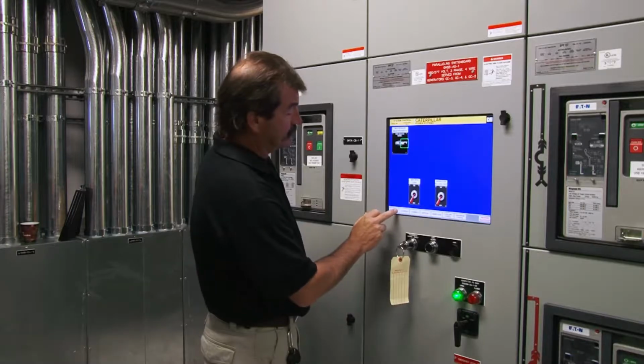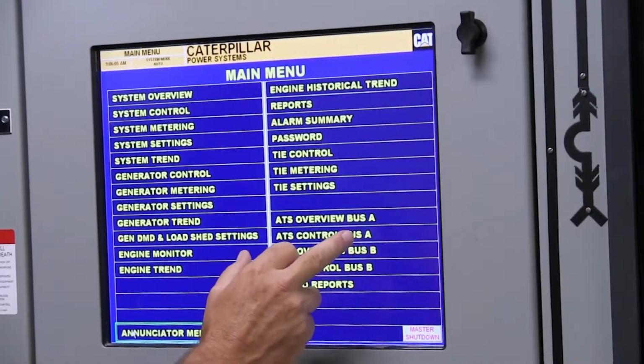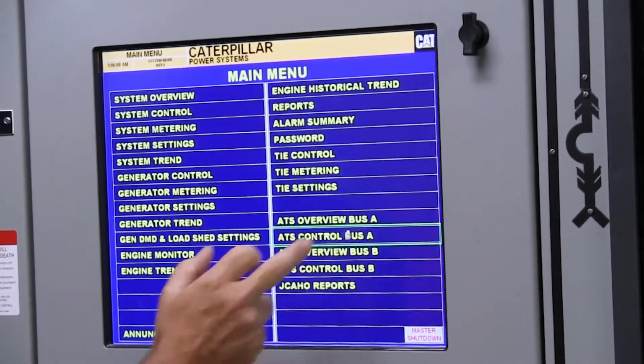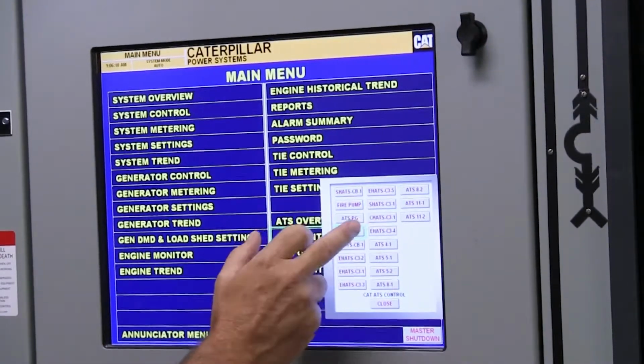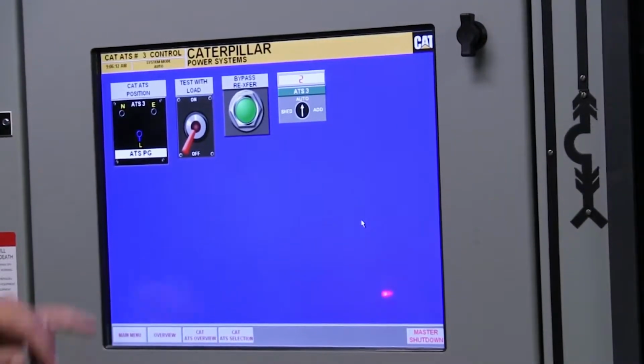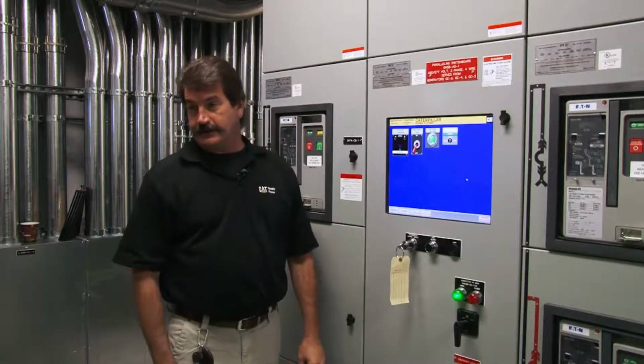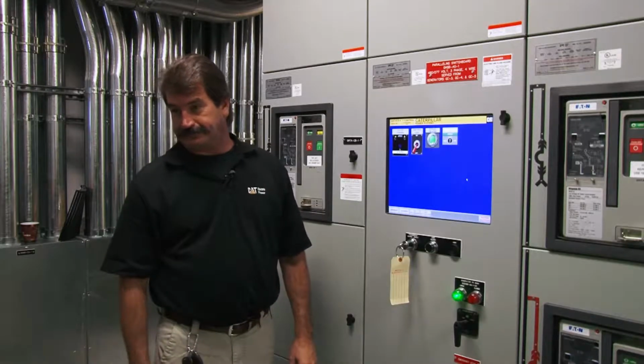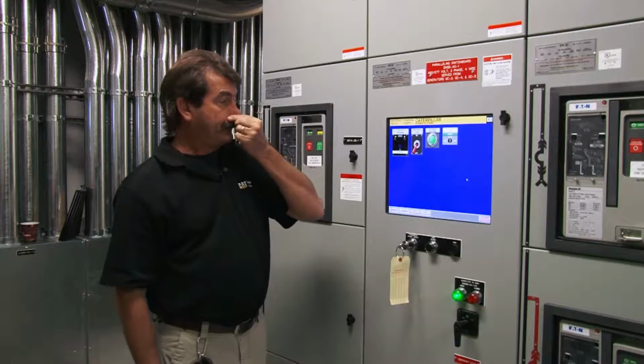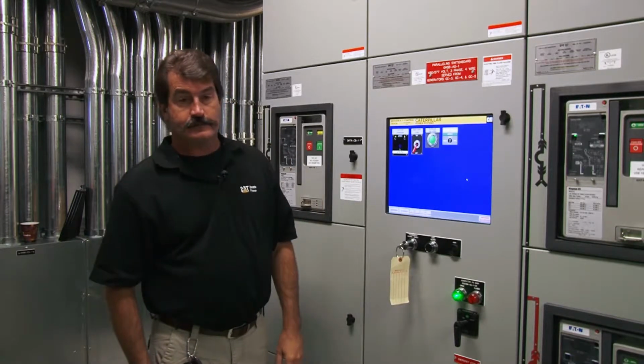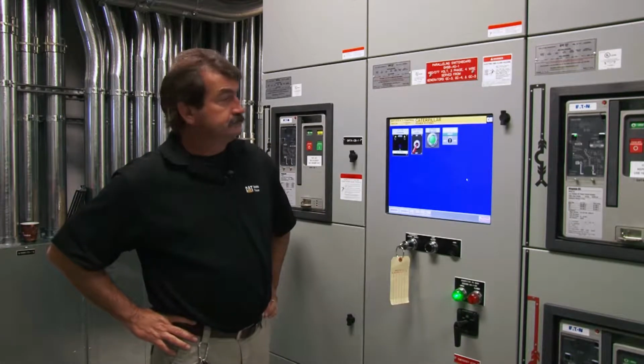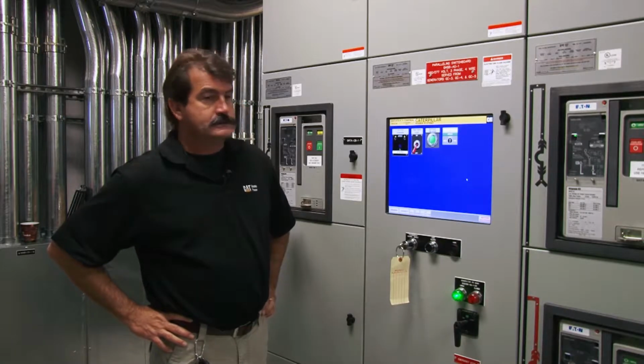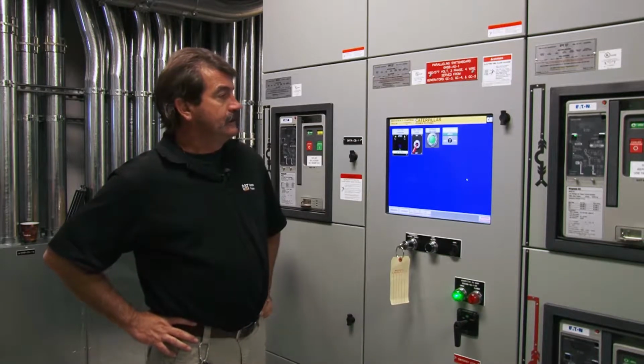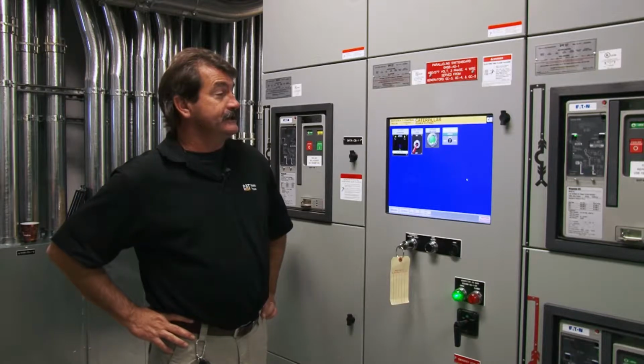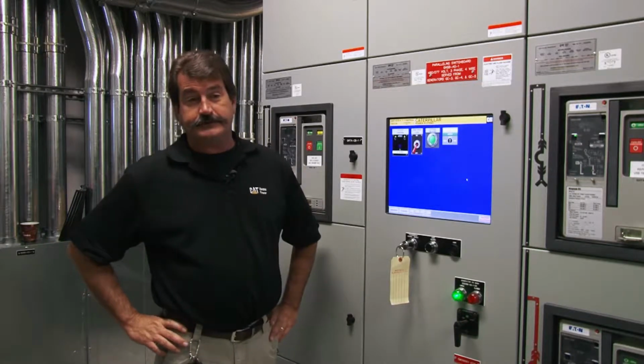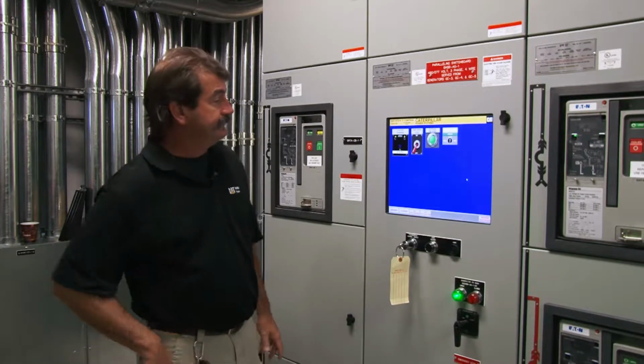So if we go and look at the ATS control bus, that's going to do your test with load. What's that number 2 on that? It's 2 generators - that's when the second generator comes online. That's saying that ATS is not going to swap until you get the second generator on.